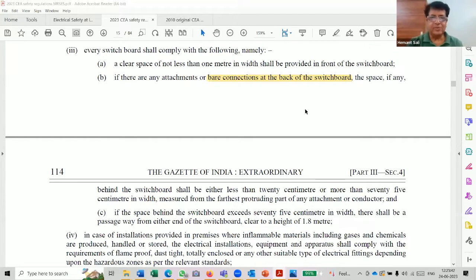If we go as per the word, the recommended thing, we cannot say it's mandatory. So that is just the recommendation. But if the electrical inspector gives an order that this thing should be as per this, then that becomes mandatory. So that is actually the discretion of the electrical inspector. If you see section 136, any order given by the electrical inspector not followed becomes punishable. So the electrical inspector can order that recommendation, and he can convert it into an order and make it a mandatory part.